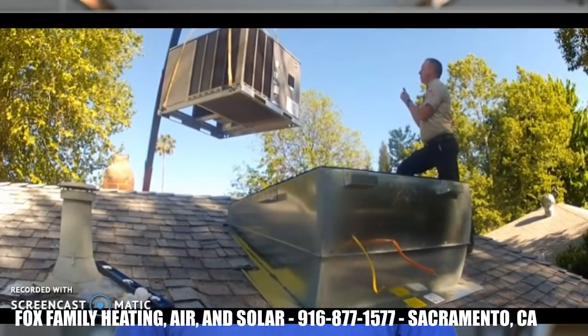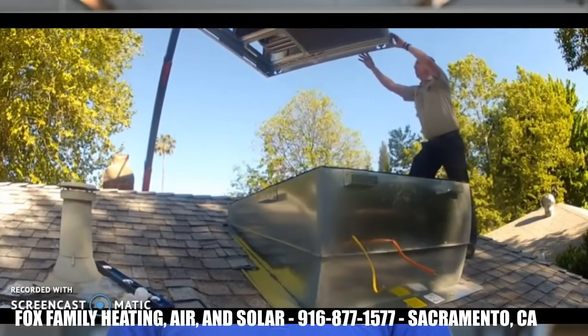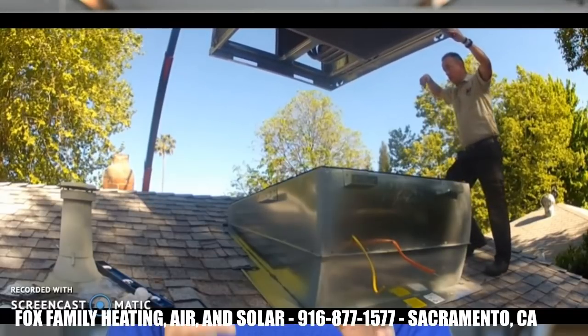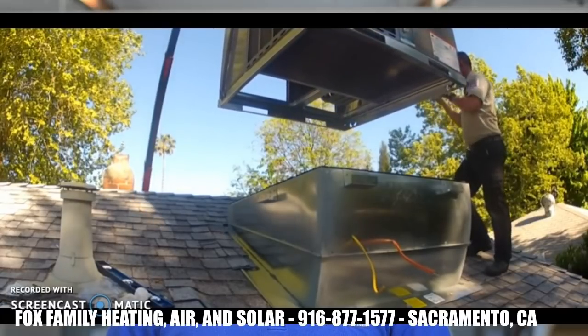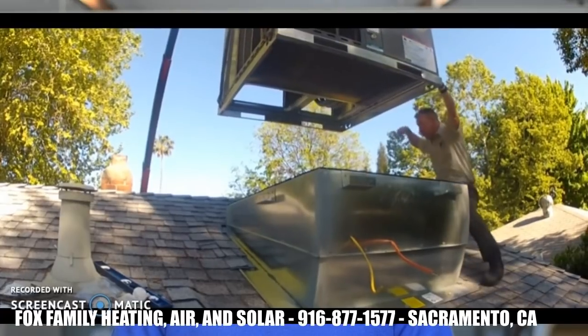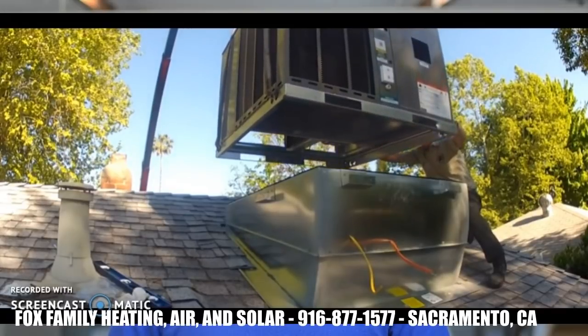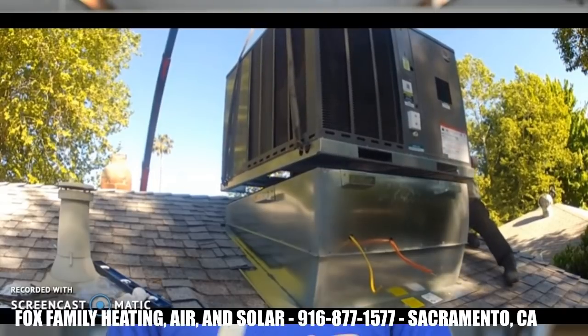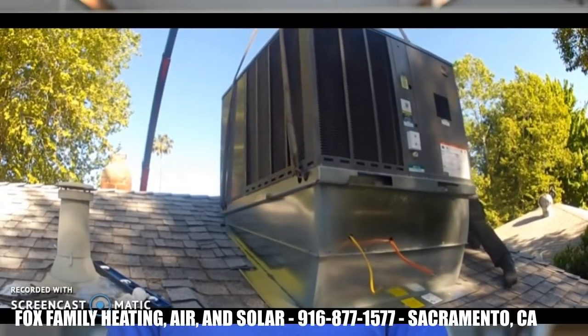Another concern with having a package unit on the roof for some homeowners is whether the package unit is secure up there. First, in terms of how it's mounted to the house so that it doesn't slide off the roof — a stand is installed on the roof with lag screws mounted into the roof joists, and then it's weatherized to prevent leaks. An adjustable curb can also be used and flashed into the existing roof shingles. The package unit sits level on top of that stand or curb, and metal straps hold it down so that it's earthquake proof.